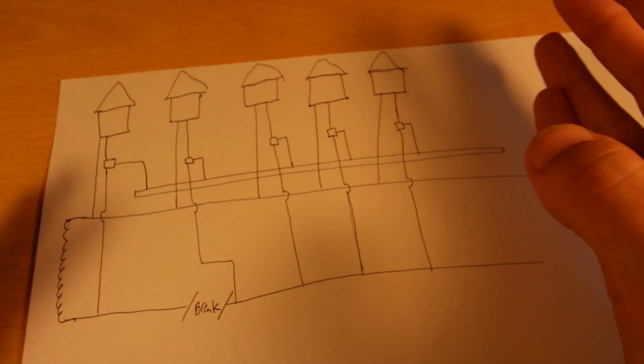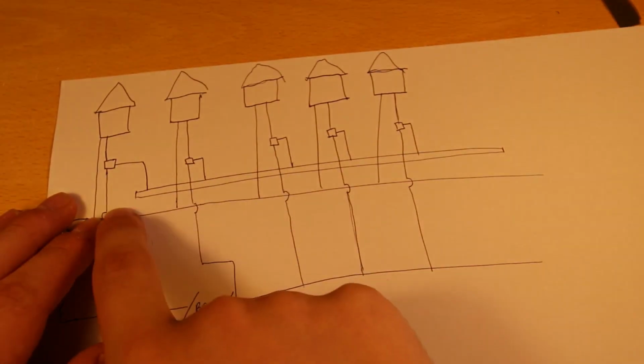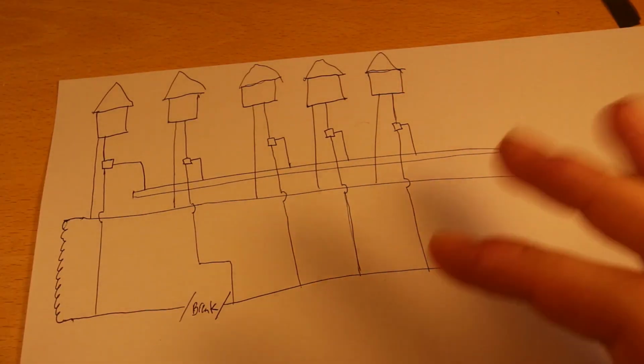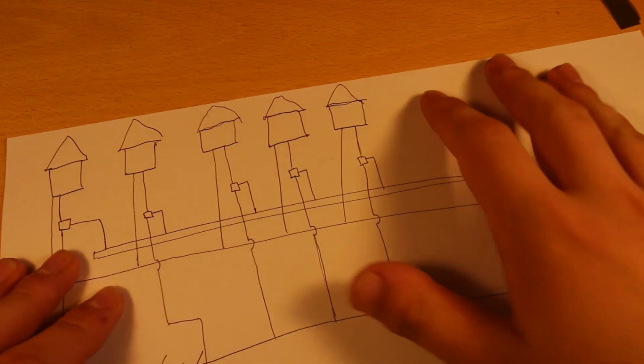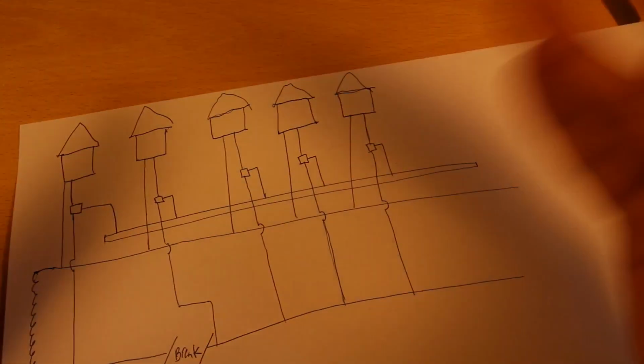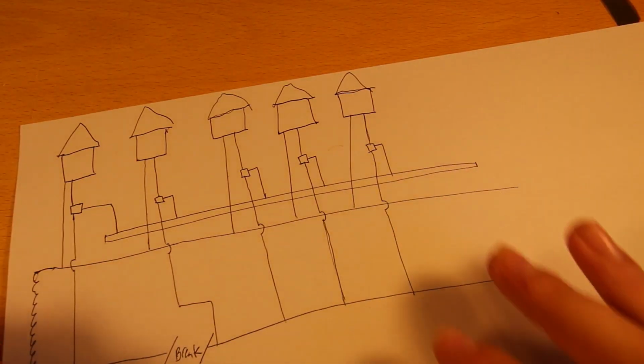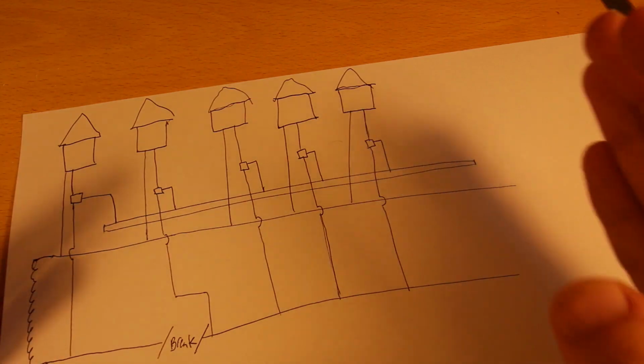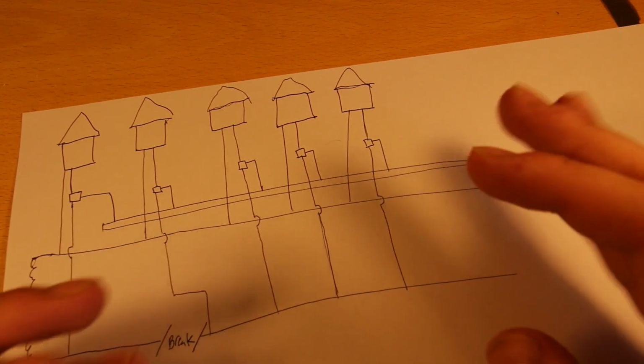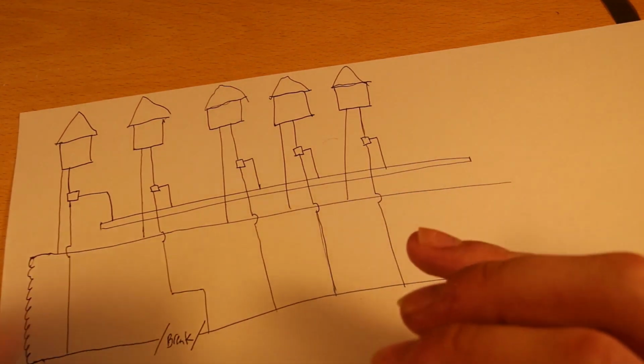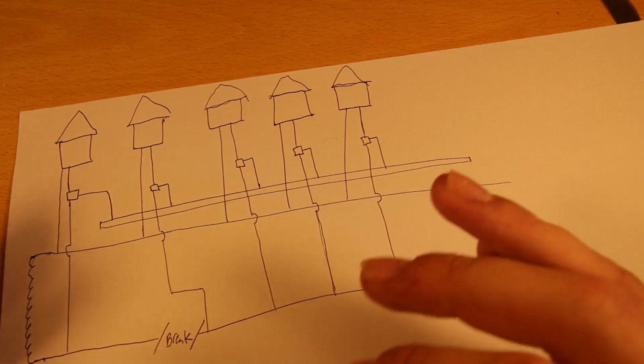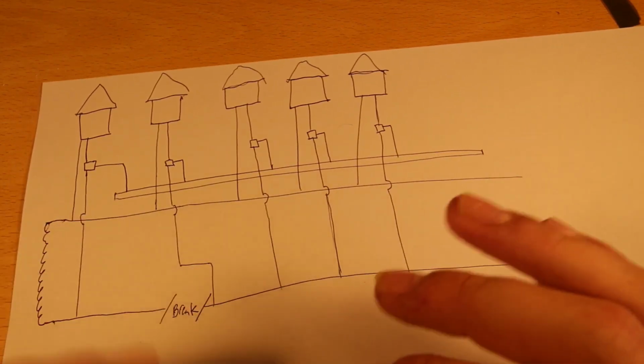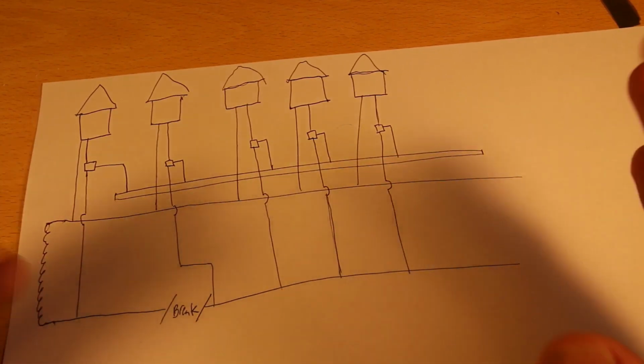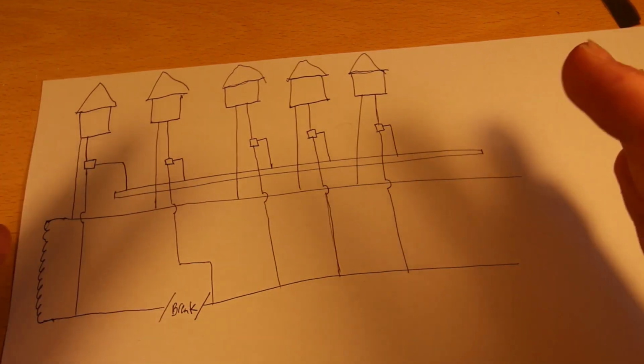So what will end up happening is this water main, or gas main, or whatever it is, will end up carrying the full neutral current of the entire street. Or multiple houses. It depends on exactly where the break happens and things like that. But obviously a pipe is not designed to carry current, so they will get hot, they can go on fire. There have been fires and explosions from gas mains, and it's not good.